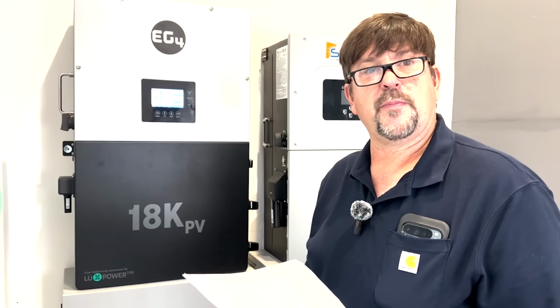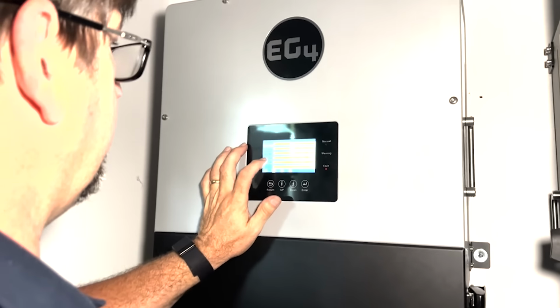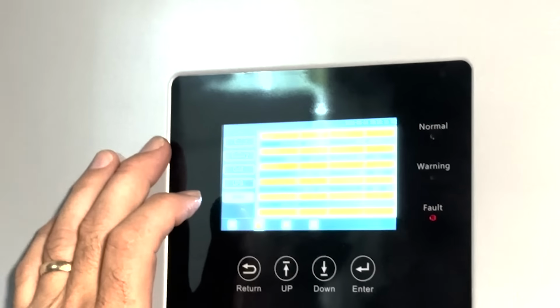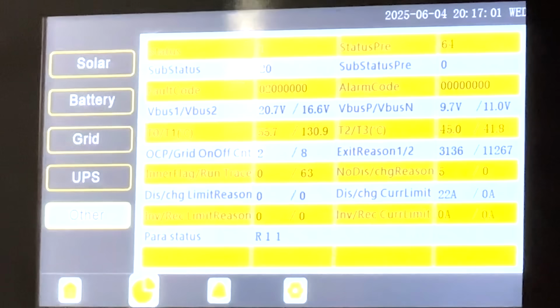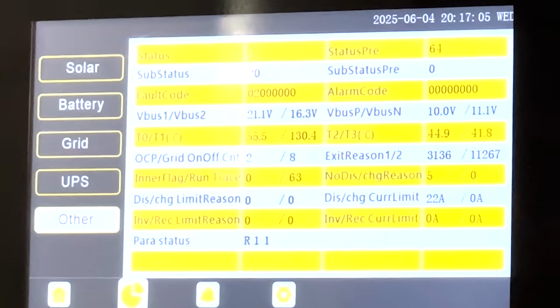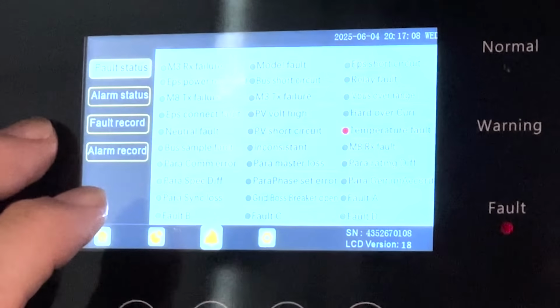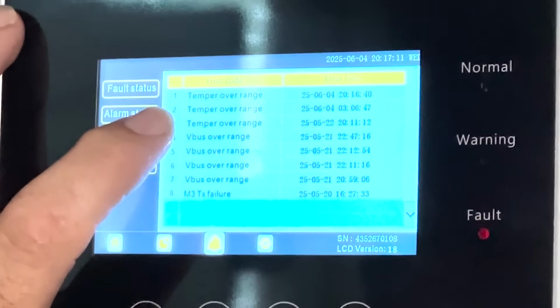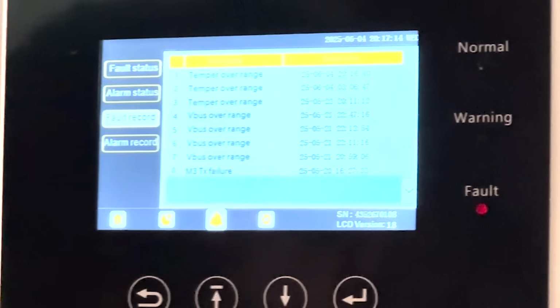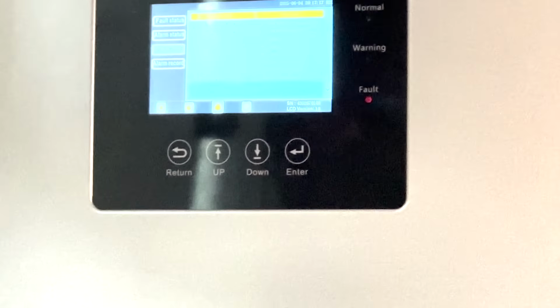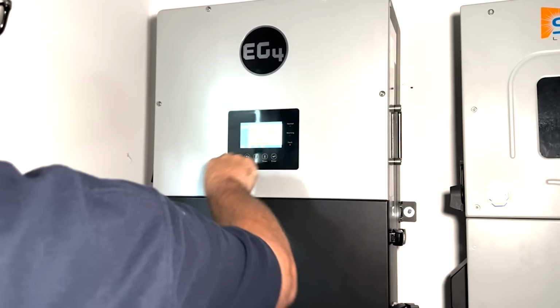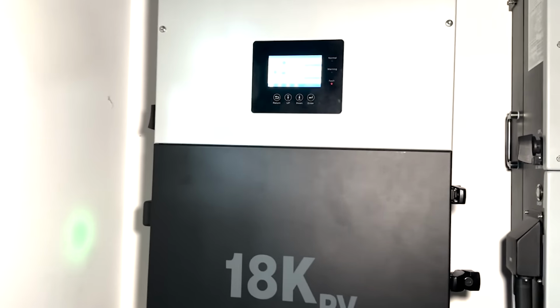Okay, as we continue to try to figure out what's going on with this, you'll see there's a fault on the inverter. We got up to 131 degrees centigrade, and it did finally shut down. The first time the inverter got up to 120, I called EG4, actually Signature Solar, and asked them when does this thing shut down, because we've had several over temps and faultings on doing this test, which made me real nervous. They did get back to me via email, thankfully, and they said at 120 degrees it should shut down. However, this did not shut down on the third overheat till it was 131 degrees centigrade.